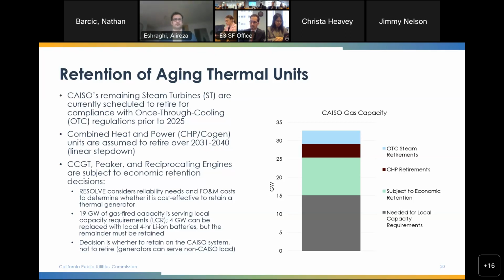Of those 25 gigawatts, 19 gigawatts of gas-fired capacity is assumed to serve local capacity requirements in local areas. Of that 19, 4 gigawatts can be replaced with local 4-hour lithium-ion batteries, but the remaining 15 must be retained. So in the chart on the right, you see a 15-gigawatt floor of aging thermal units that must be retained, and the balance is subject to economic retention decisions. The decision is whether to retain the gas units on the CAISO system, not to retire them. The generators can still serve non-CAISO load.